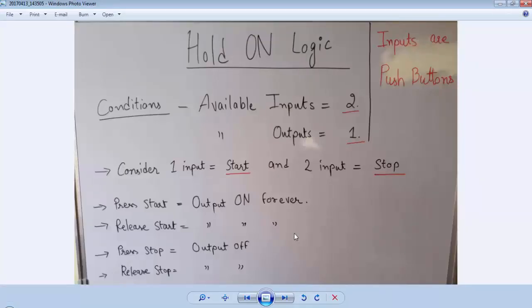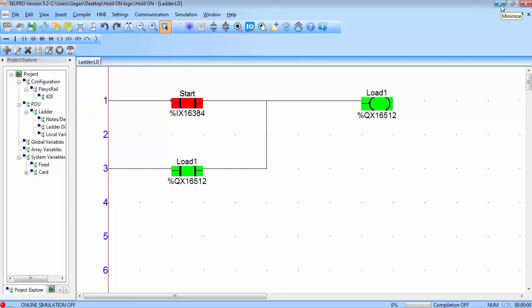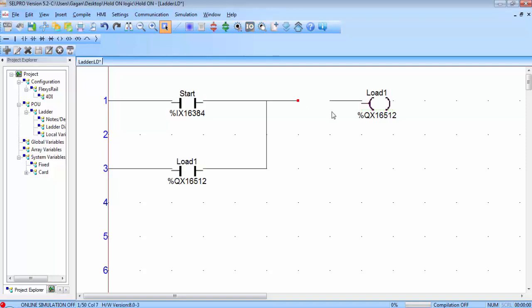To achieve the second condition — turning off the output — we need another contact with a stop button. That is why we need two inputs for a hold on circuit: one for start and one for stop. Delete the horizontal line and place a NC contact, which will work as the stop button. Assign the next input address, IN1 of slot 1, to this NC contact.